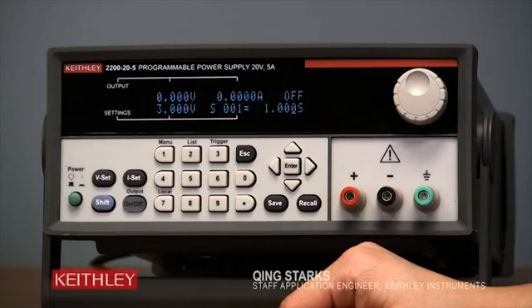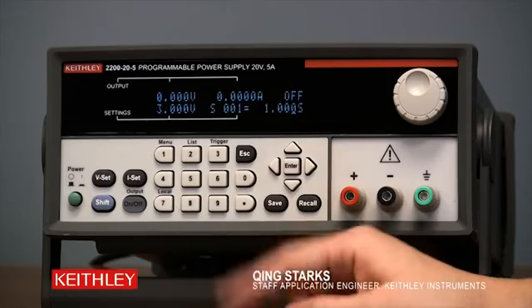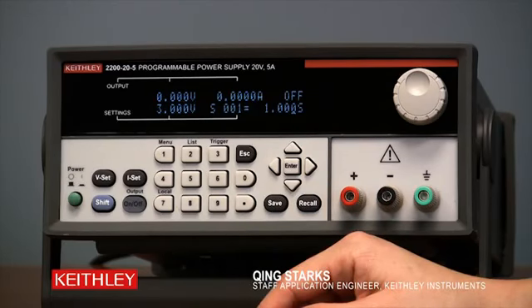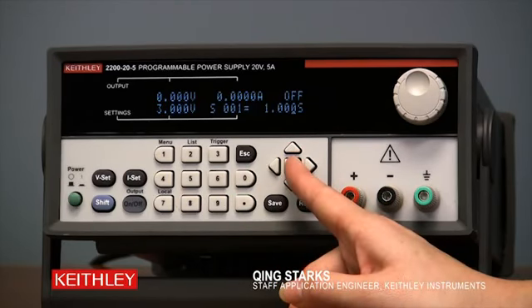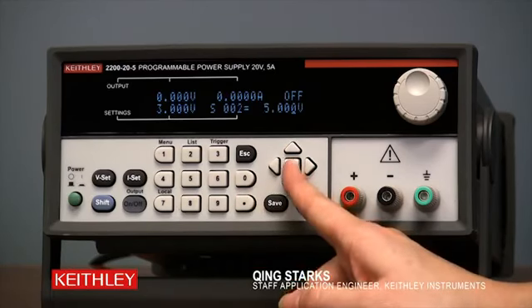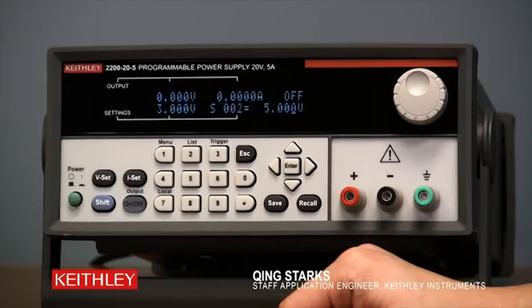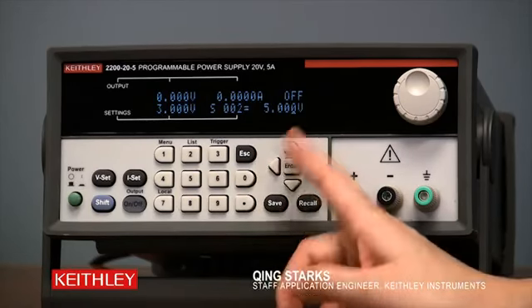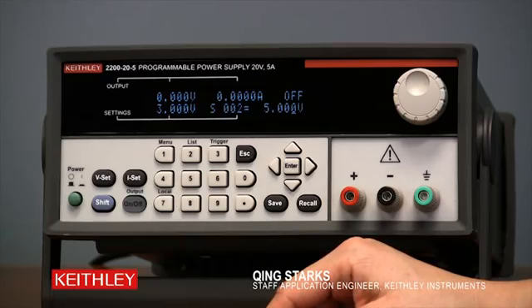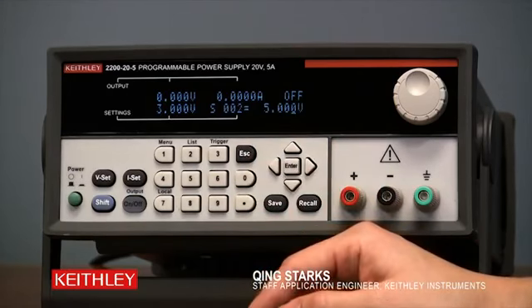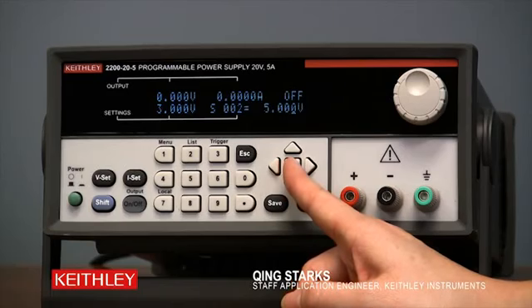The last step in this voltage setting is the time duration. It is currently set to 1 second, and we're okay with that too, so we'll just press Enter. Now the display is prompting you to enter step 2 of the list. In step 2, we're also setting the voltage at 5 volt, and the display is showing 5 volt. We'll just press Enter.